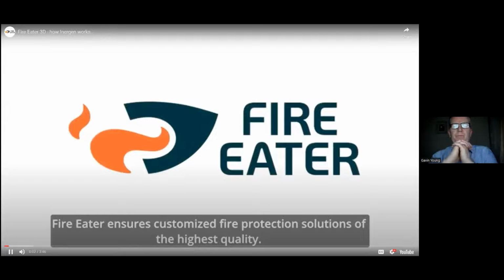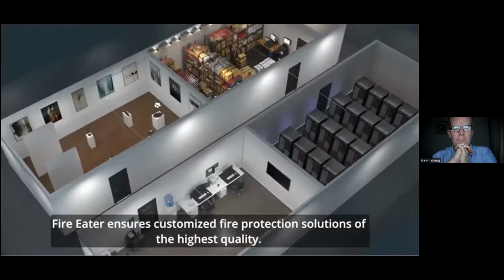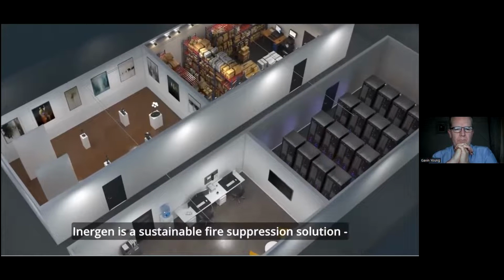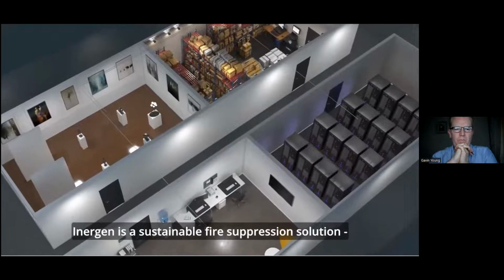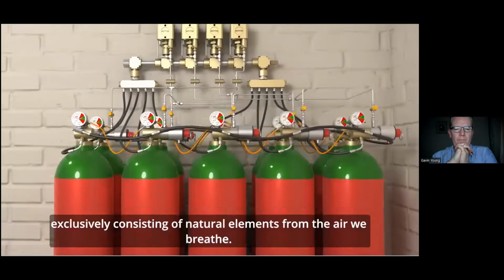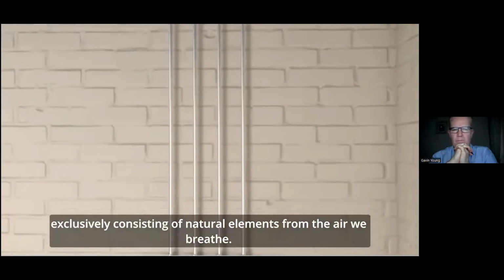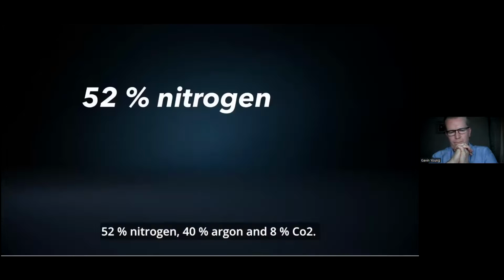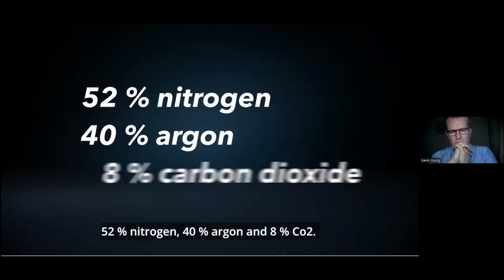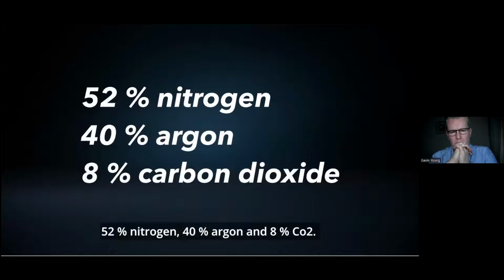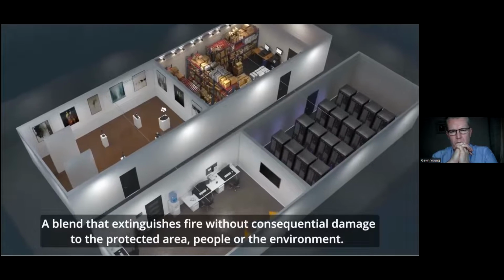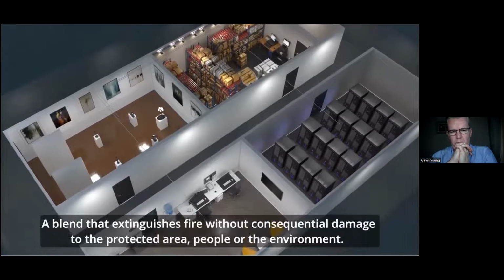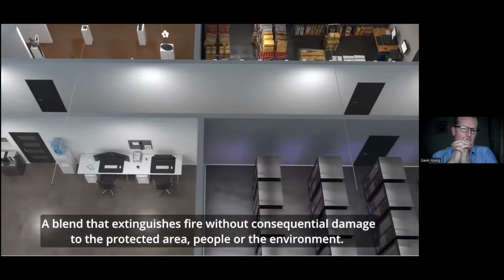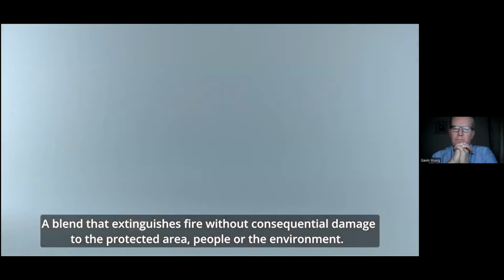Fire Eater ensures customized fire protection solutions of the highest quality. Inergen is a sustainable fire suppression solution exclusively consisting of natural elements from the air we breathe. 52% nitrogen, 40% argon and 8% CO2. A blend that extinguishes fire without consequential damage to the protected area, people or the environment.